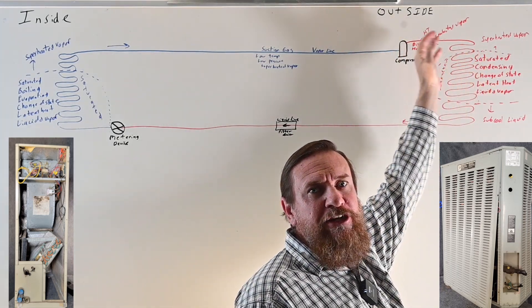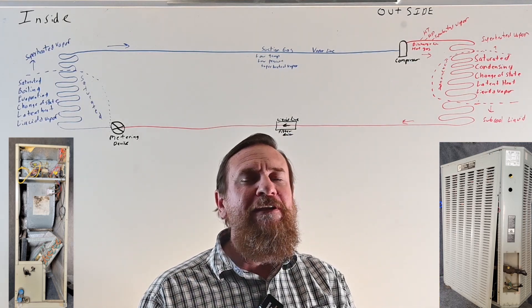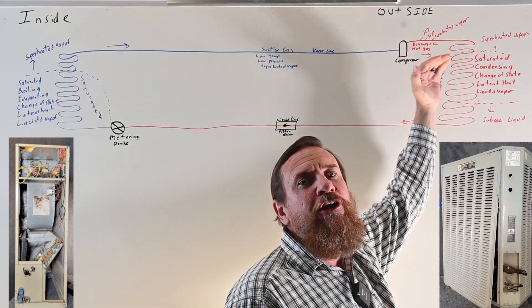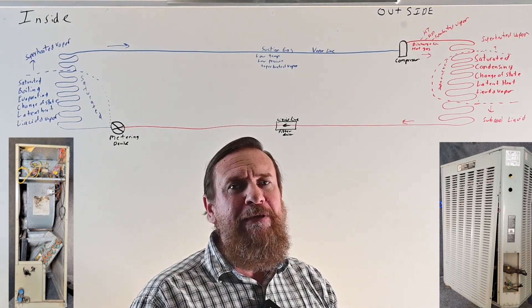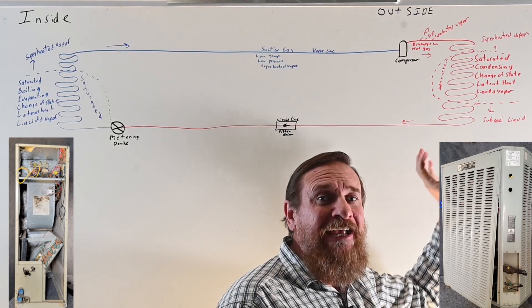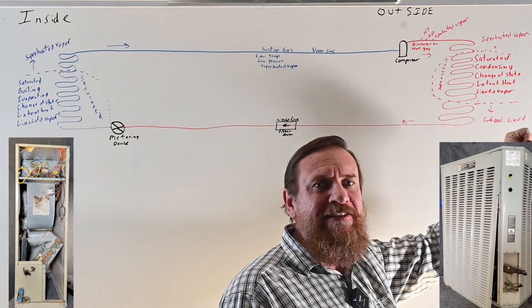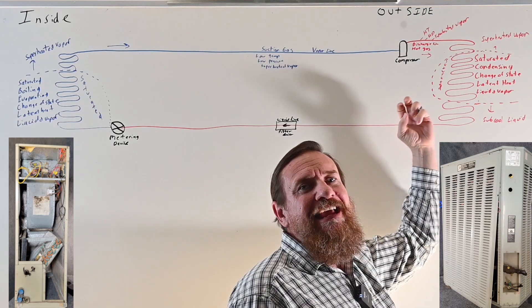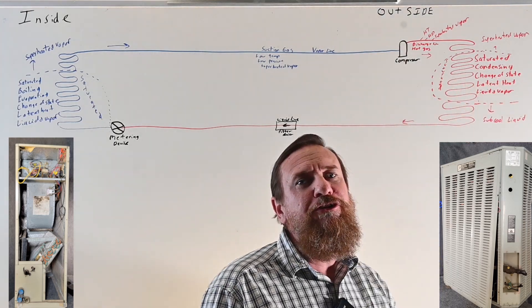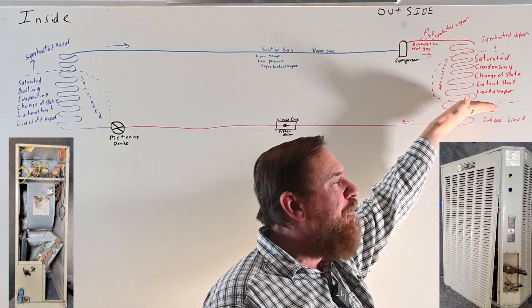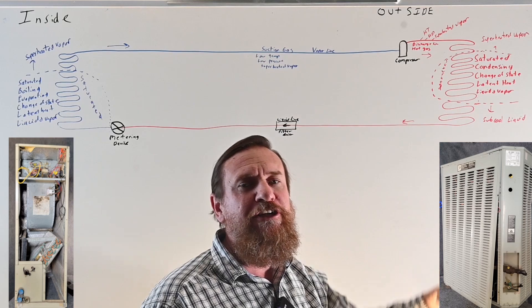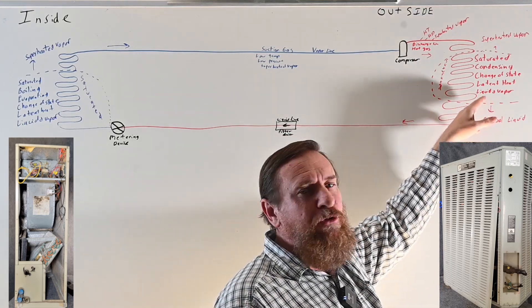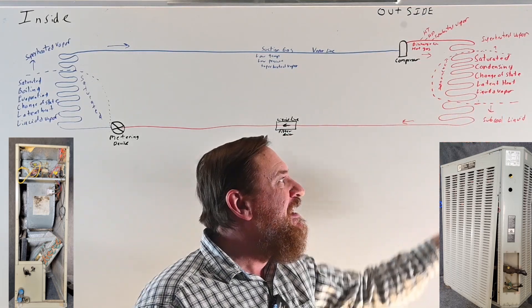From there, we de-superheat it and get it back down to saturation. That's a high number but a very small amount of overall heat. The magic is where we make that refrigerant change state from a vapor to a liquid — that's the mass amount of BTUs happening. The compressor raises the temperature higher than the outdoor temperature, say 120 degrees when it's 100 outside, so heat leaves the warmer refrigerant to the cooler air. We can then sub-cool the refrigerant below saturation, say about 10 degrees.